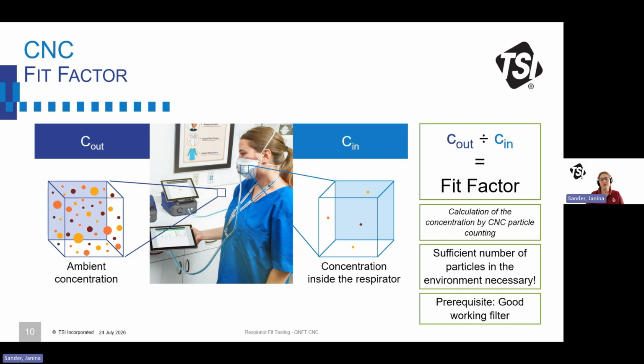In general, CNC is the abbreviation for condensation nuclei counting. The ambient concentration, as well as the concentration inside the respirator, is calculated from the flow of the measurement instrument and the number count of particles that the instrument counts in the air. In general, it is important for this fit factor idea that you have a sufficient number of particles in the ambient concentration.